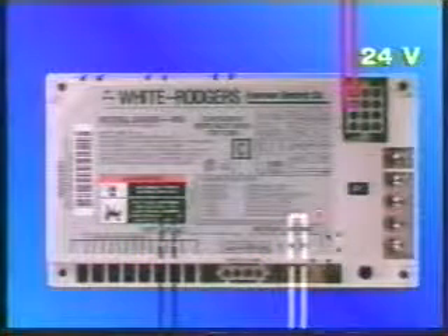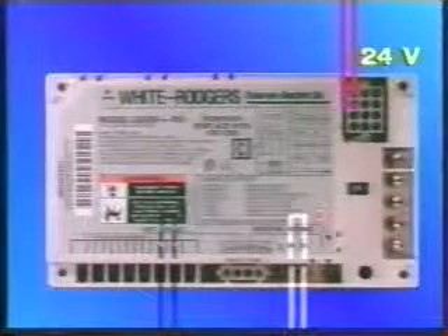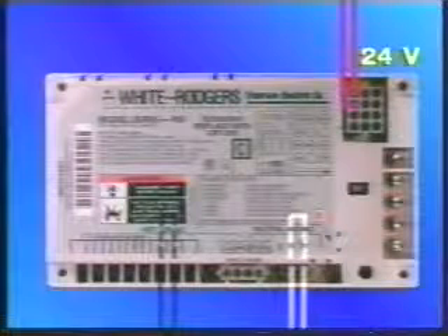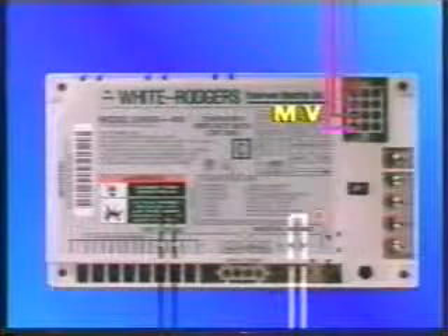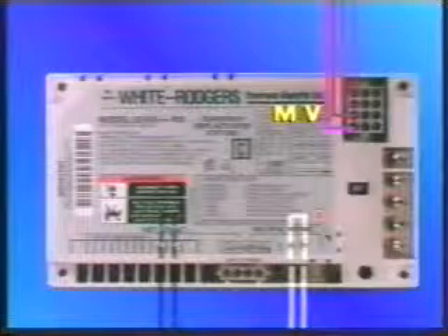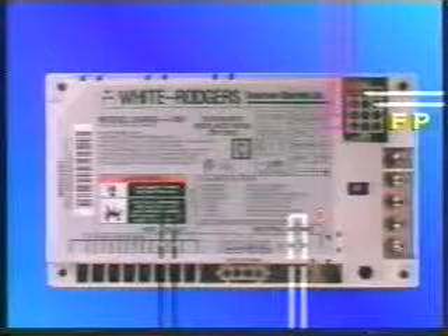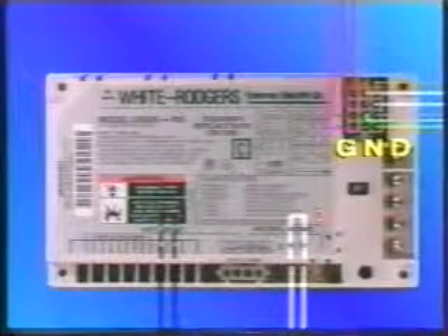The secondary side of the 24-volt transformer is connected at a 12-pin connector. The gas valve coil is connected to the MV terminals through the 12-pin connector of the control module. Similarly, the flame sensor probe is connected to the FP terminal at the connector. The connector also houses the limit switch terminals, the pressure switch connections, and the rollout switch connections if needed. The GND terminal is connected to chassis ground. This connection must always be connected to the electrical service ground.